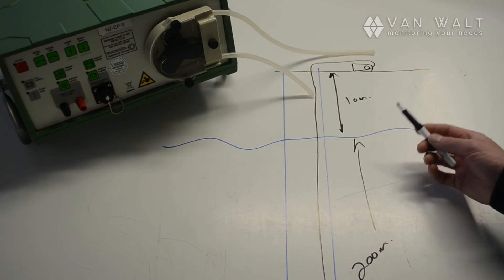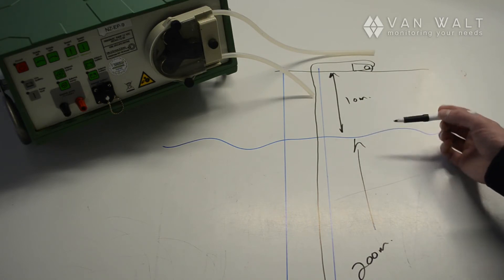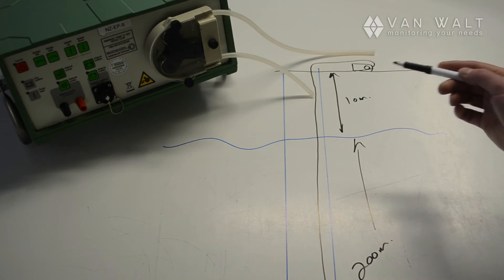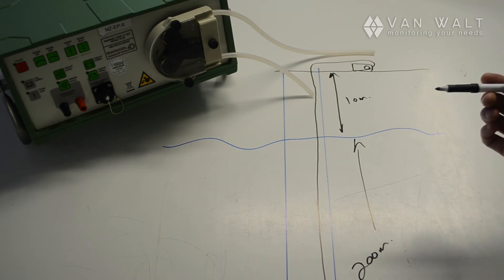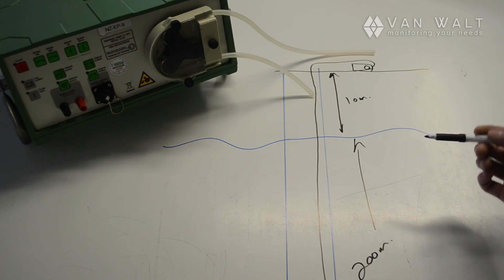You have potential loss of VOCs when the lift gets higher, but those losses can be acceptable and quantifiable. The alternative to this pump may be a bladder pump, but it's much harder to use and therefore much less repeatable. This is a very easy pump to use and easy to set up, so if you can accept that there will be some losses of VOCs in your sample, you may get more repeatable results in the long term.